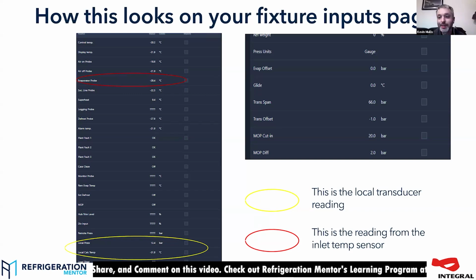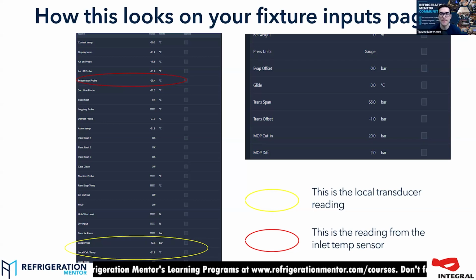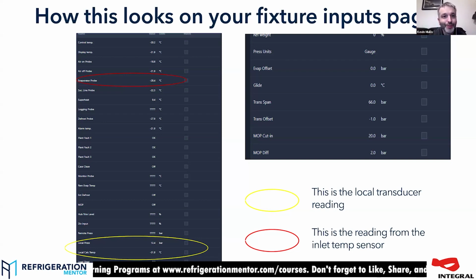The problem with the inlet probes, especially where we pretty much always have, unless they're really small coils, a distributor and thin legs going into the coil, is there's often nowhere good to mount the probe. I see people all the time mount the probe on the little bit of pipe after the expansion valve before you get to the distributor. That's not a good place to mount it, because you're at an intermediate condition in there. When you drop through those distributor legs, you get pressure drop. So the condition the gas is evaporating at when it leaves the valve in that little bit of pipe is not the same condition the coil's seeing. But people put it there because it's the biggest bit of flat pipe to mount the probe on, right?